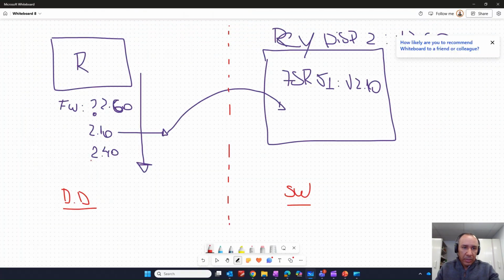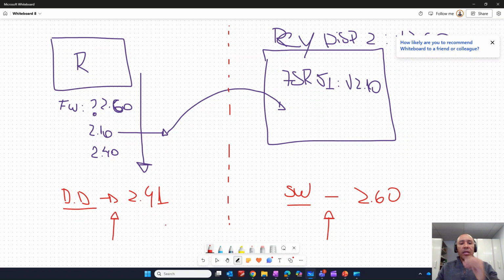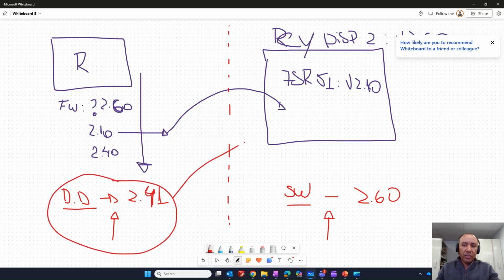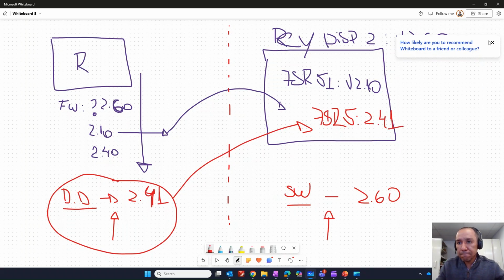In this particular example, I have one file that's the device drive with version 2.41, and the software on 2.60. First, I recommend that you install this, and after that you install this one here. Basically, the software is going to import this device drive inside of this version of the software in order to configure the relay 7SR5 on version 2.41. Okay, I think that was clear. And now let's get inside of the software.